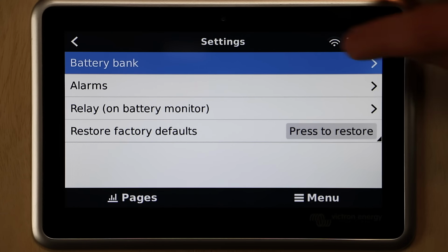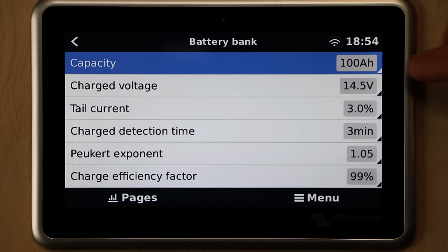So we actually have to give it some settings for the battery bank. We have a 100 amp hour battery. The charge voltage is going to be the bulk charge voltage from your battery manufacturer. 14.5 works well for lithium batteries, and it's going to use these first three parameters in order to reset to 100% state of charge.